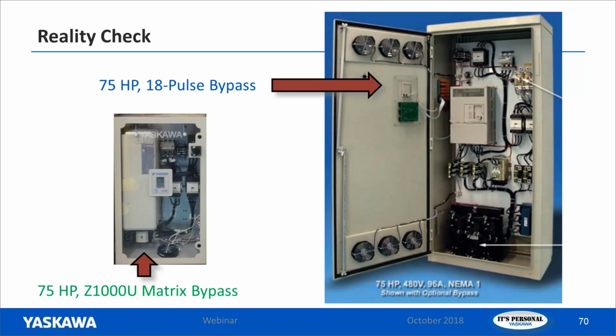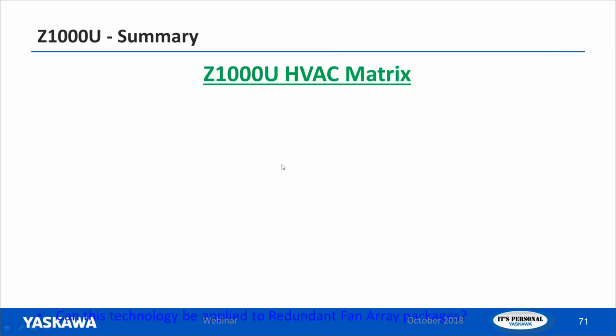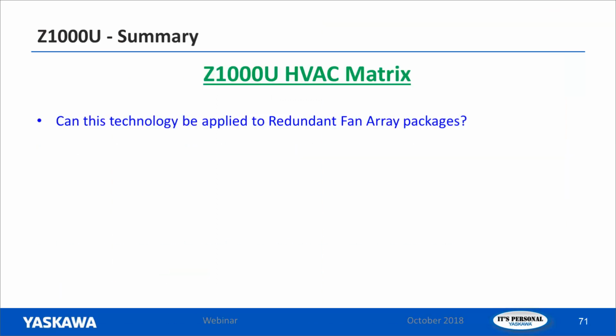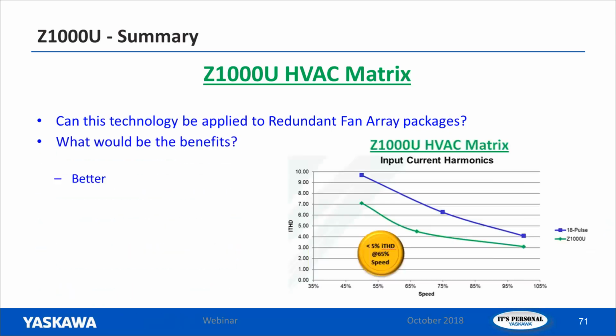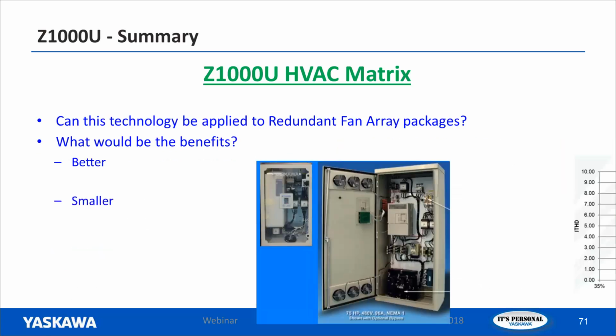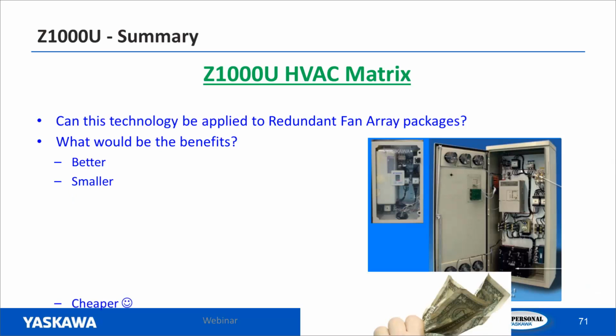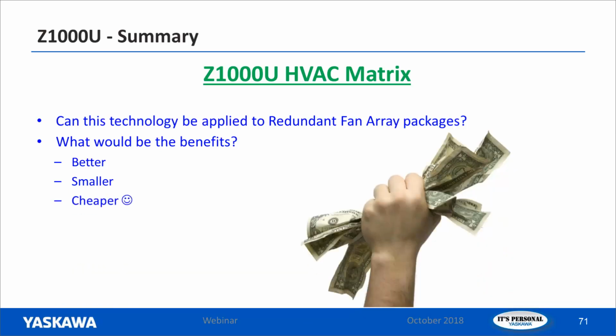And over here on the right, we've got same thing, 75 horsepower Z1000U matrix bypass drive, 3-contactor bypass. This package over here on the left is doing everything the package on the right is doing, except it's doing it better and cheaper. And this is to scale, by the way. This drawing on the left is to scale to the one on the right. So can this technology be applied to redundant fan array packages? And what would be the benefits? Well, I've already shown you that it is better, and it's also smaller, and it is less costly.